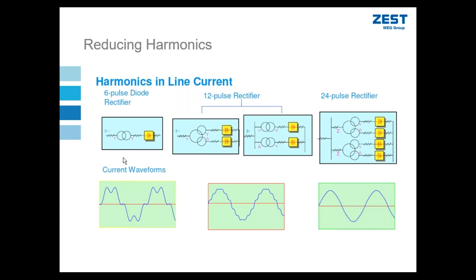Okay, then just to introduce a few other ways to do it. So the standard 6 pulse diode rectifier we've already mentioned needs only one secondary winding to supply it. From a 12 pulse scenario, I mentioned that we need at least 2 secondary windings, which is shown in the first diagram. But there's a few ways I can achieve it. I can have a single primary and 2 secondary windings. Or I could have 2 separate transformers, each with its own primary and secondary. So you can see here we have a star to star and a delta to star. That's another way to do 12 pulse phase shifting.